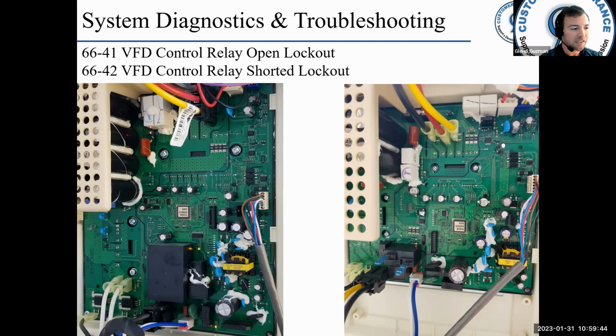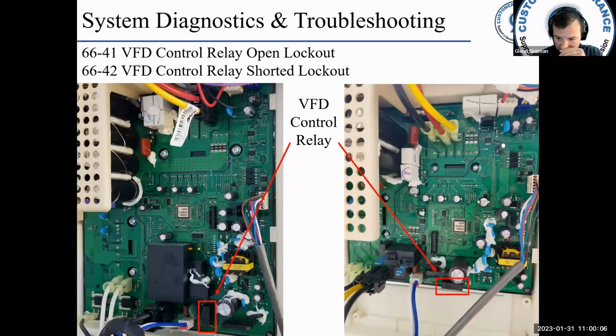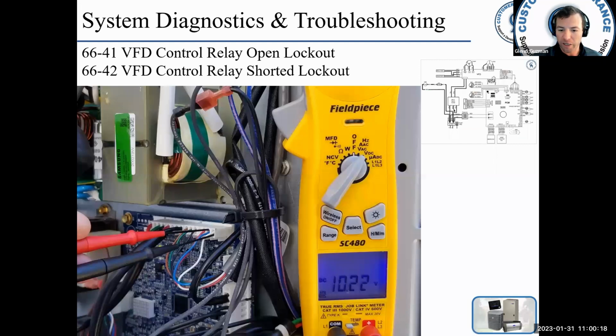12 volts DC is fed from pins 6 and 7, blue and white, of the PCM into the blue and white on the VFD. Okay, so here is your VFD control relay. All right, this VFD on the left would be like a 5-ton, and the VFD on the right would be like a 2 or 3 ton. It's similar for the 4-ton. Okay, but there's your VFD control relay. All right, now you can't physically check in that relay, but we can get pretty close.